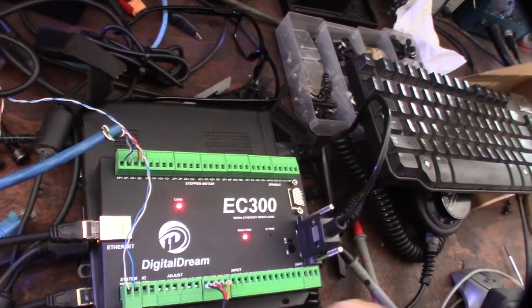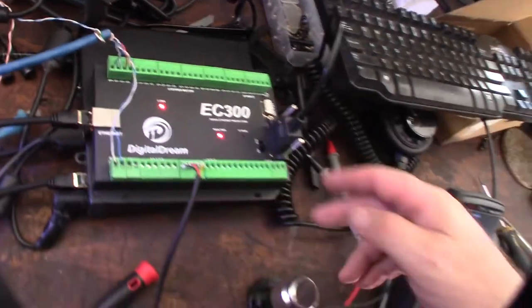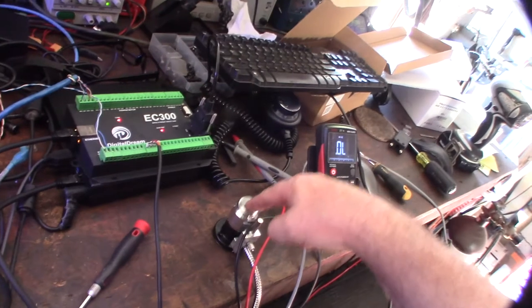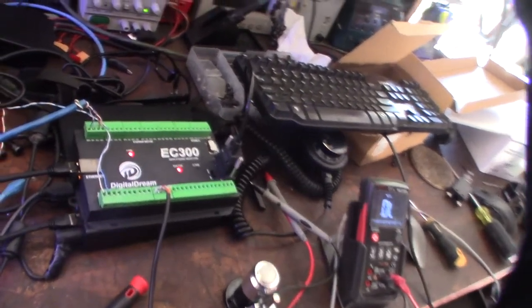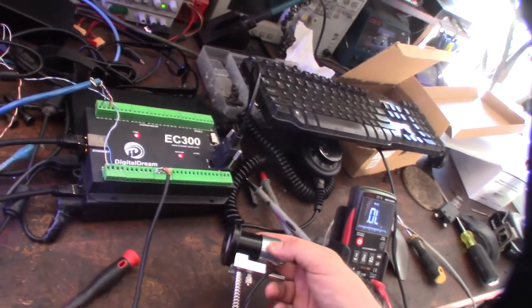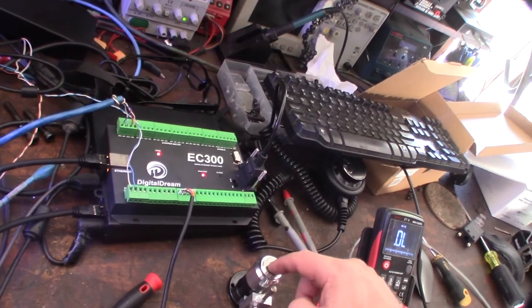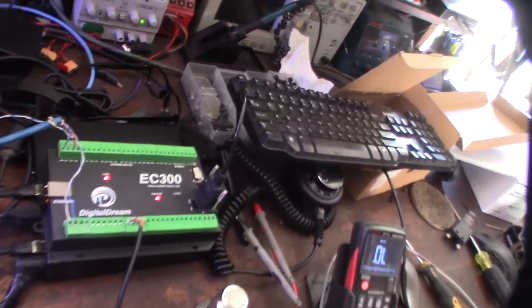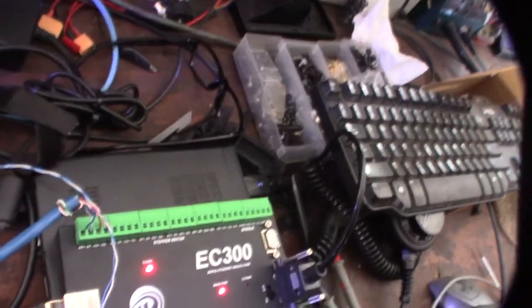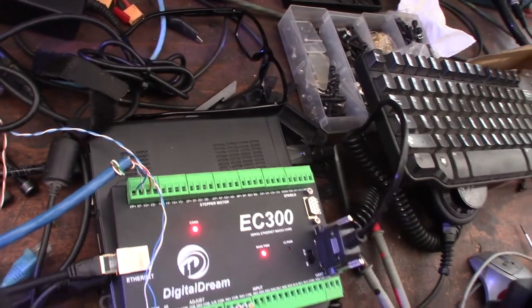All right, so I had to run a jumper from the comm to the ground. So I'm trying to get my little sensor going right now. And, yeah, these are normally closed. So one is e-stop, one is a sensor, and one is the over-travel that comes to the e-stop. So, yeah, I have to run a ground jumper.